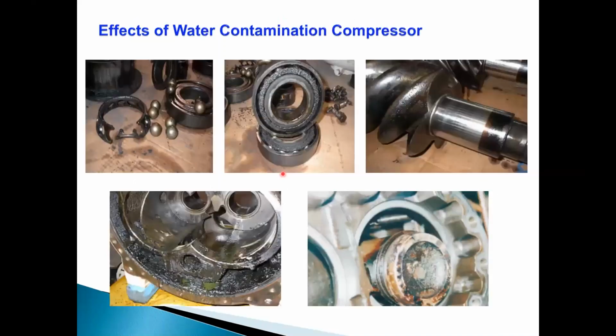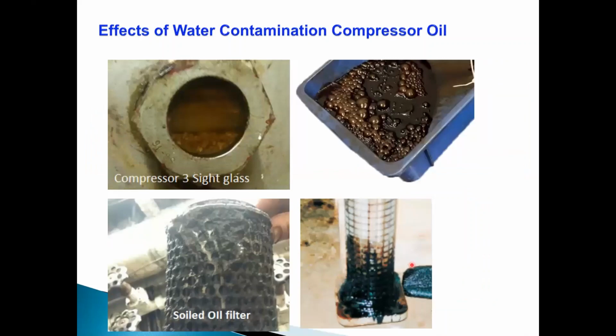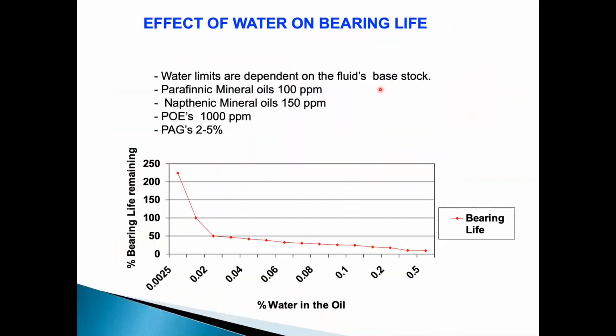See, these are some photographs showing the effects of water and sludge formation on the compressor, whether on the bearings, the screw, or the body. You can see the piston and the crankcase, and how the sludge and water contamination damage the compressor. This photograph shows water accumulated along with the oil in the oil level of the compressor. The oil filters, this is how they get choked. This is how the water has been there along with the oil. So all this adds to your cost.